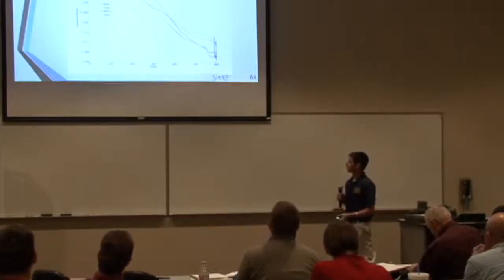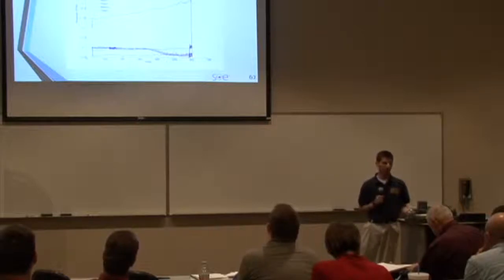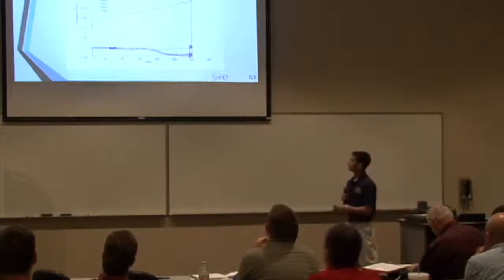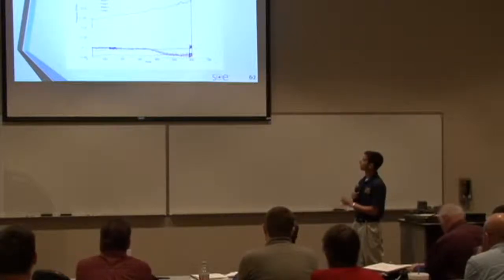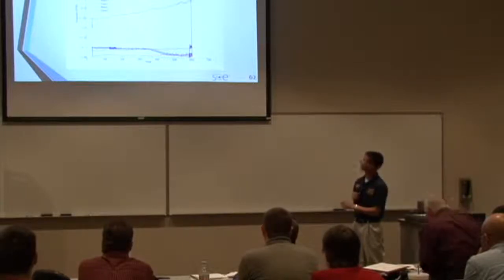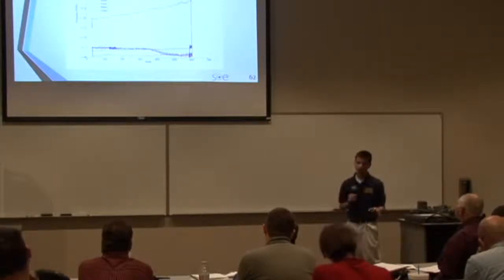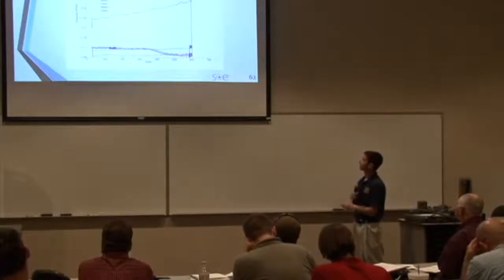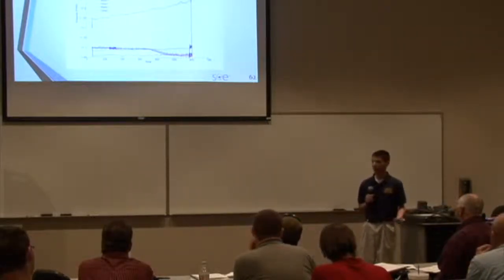So what we did from there is we brought iris up to 600 RPM and then we turned on the blower. As you can see here, it starts at about 12.1 PSI, and then we turn on the blower at just over 600 RPM. The pressure in the two total measurements, which are the ones that go up, went up to about 12.4 PSI, a little bit higher. And at that point, as you'll see in the next slide, the seal failed, so we brought iris to a stop as a standard procedure.